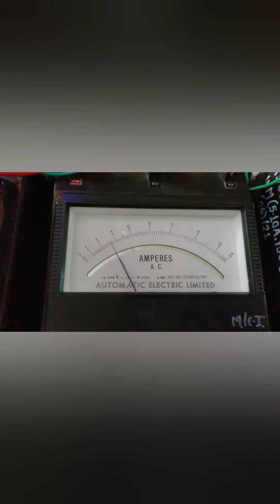So at no load test, what is the voltage, what is the current, and what are W1 and W2, that value we have to take. At 415 volt, at no load condition, the current value is coming out to be 3.8.